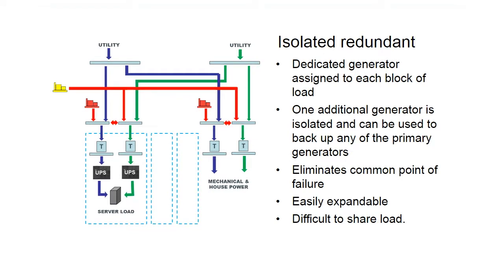Another type of system is an isolated redundant system. This is where you have a dedicated generator assigned to a block of load, and then you'll have one additional generator that is isolated from the others that can be used as a backup for any of the primary generators. This basically eliminates that common point of failure. It's easily expandable as you go. You just keep adding generators and connect them to that isolated redundant one. The difficulty here is that it's tough to share load. So if you have a generator dedicated to one block of load and it's lightly loaded, it's a little more difficult to share that load with other systems.